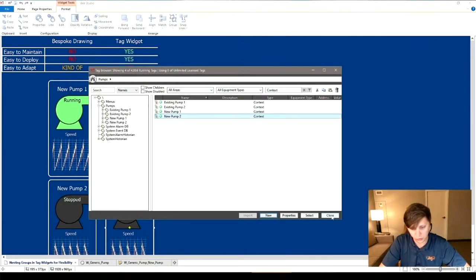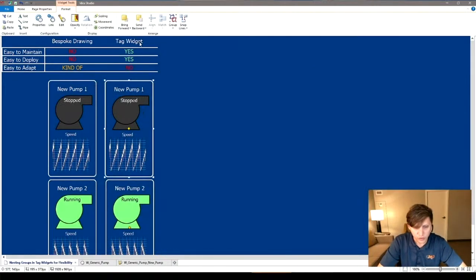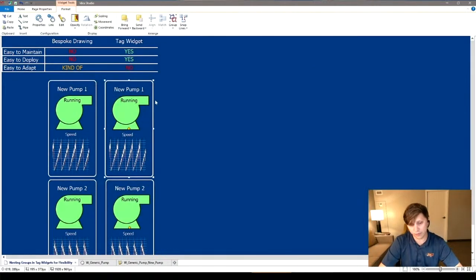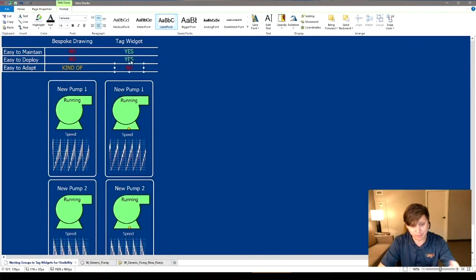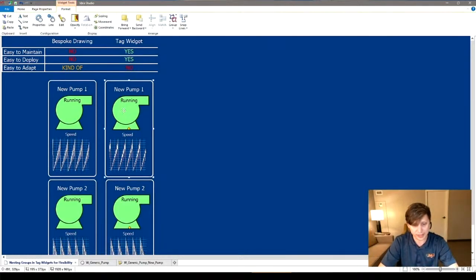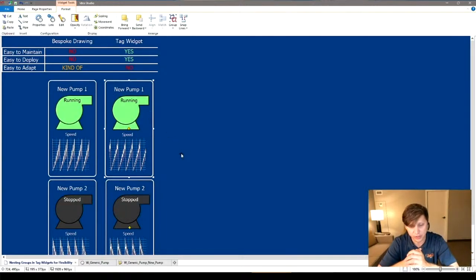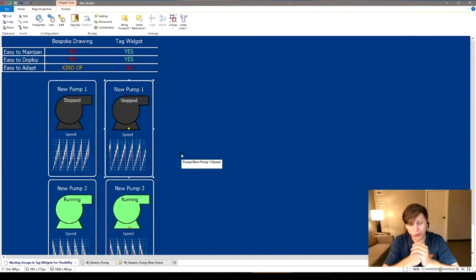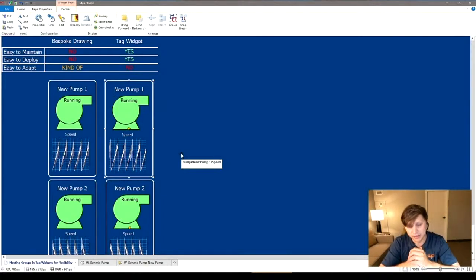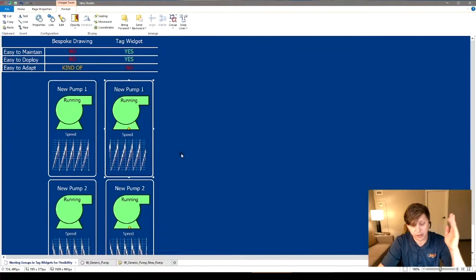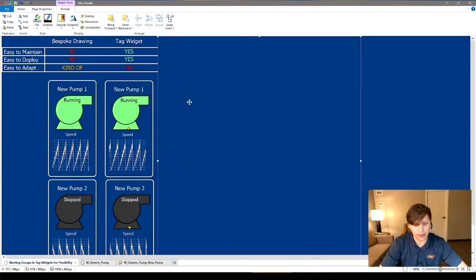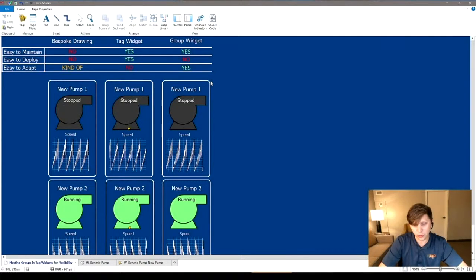That's really great—if you've got a second pump, all I need to do is link it to a pump. There's no individually going in and changing things. So it's awesome if you've got a bunch of identical tag structures—easy to maintain, easy to deploy, difficult to adapt. If you had a pump that was somehow different, like it had a tag called pump status instead of running, this widget just doesn't work—it will have an error message on it. So a way to get around that is what's called a group widget.